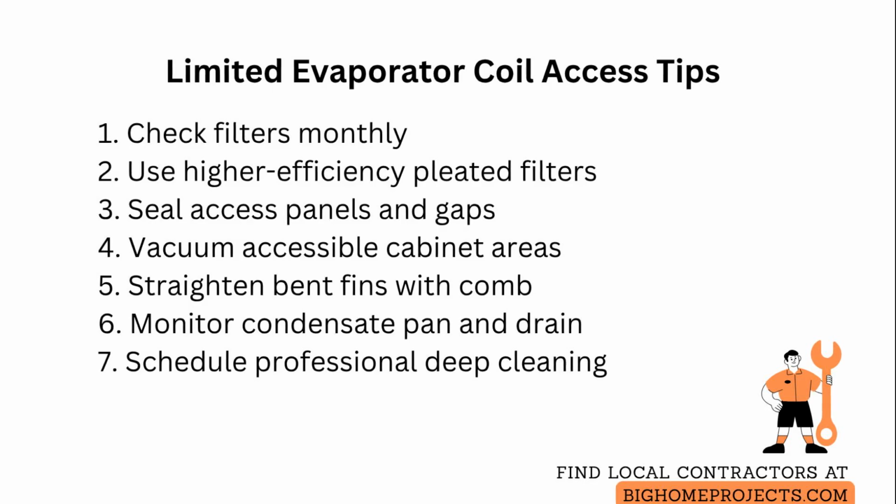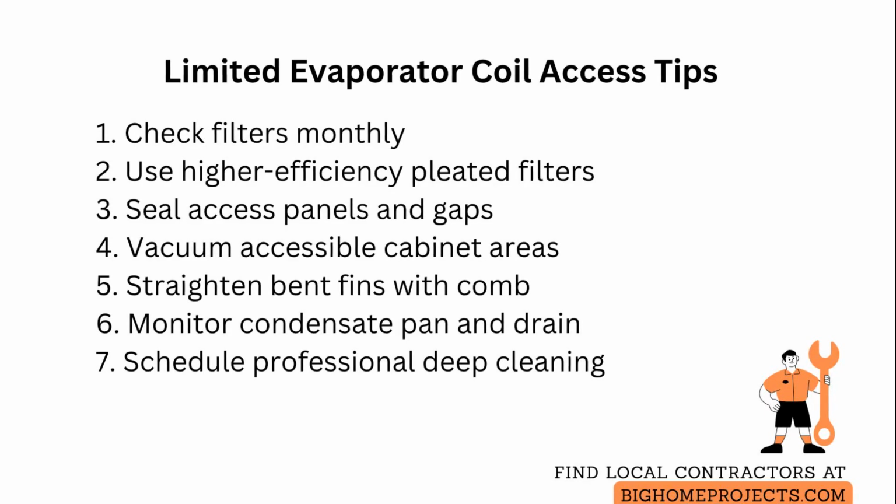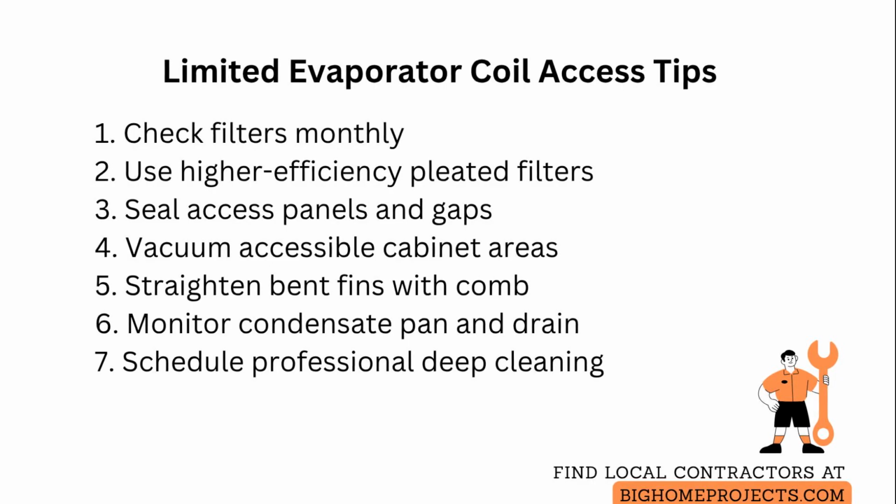If you detect excessive buildup, odors, reduced cooling, or icing, schedule a professional deep clean because technicians can remove panels, use coil-safe foaming cleaners, and perform mechanical cleaning while protecting electrical and refrigerant components.